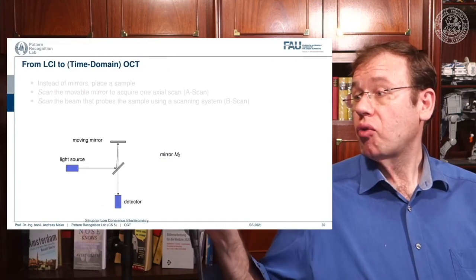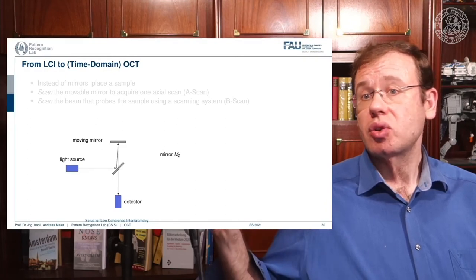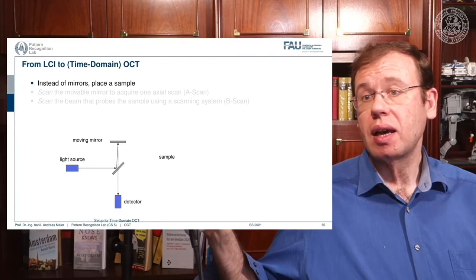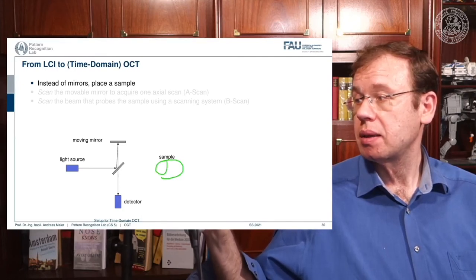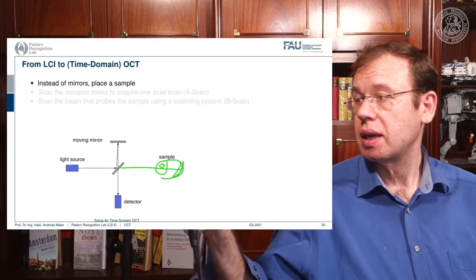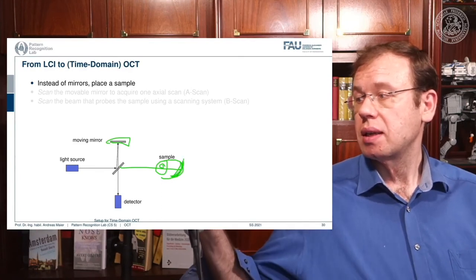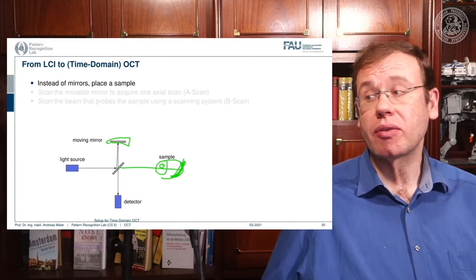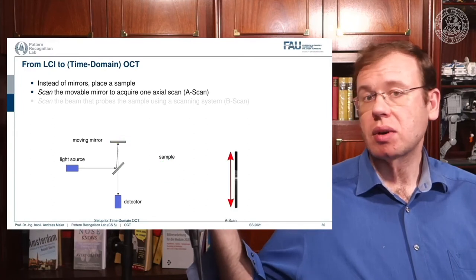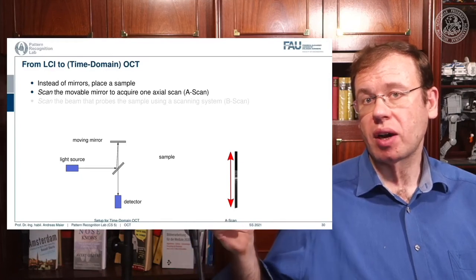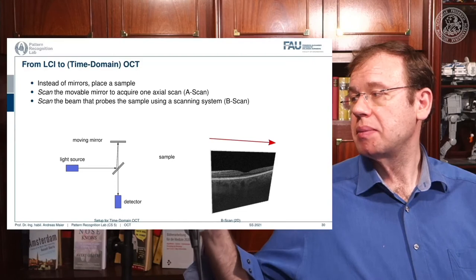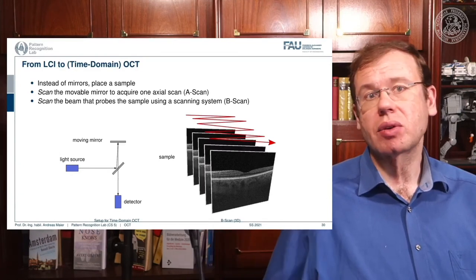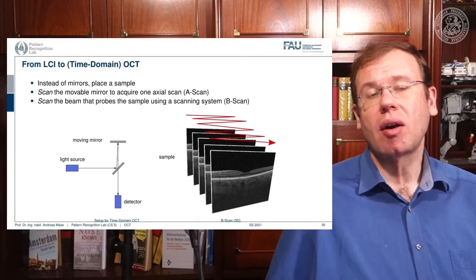We can now move from time domain OCT to a different setup where we replace the second mirror with a sample — for example, the eye — and scan the retina. Moving the movable mirror up and down constructs an A-scan, giving a depth profile along the retinal depth direction. Scanning many beams laterally gives a B-scan, and repeating that produces a volumetric scan over an entire 3D volume.